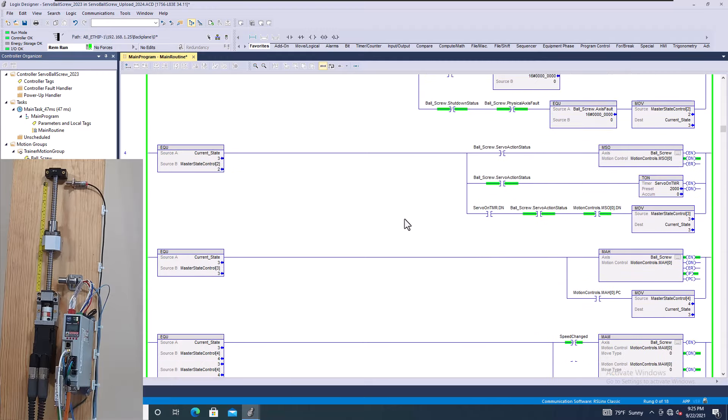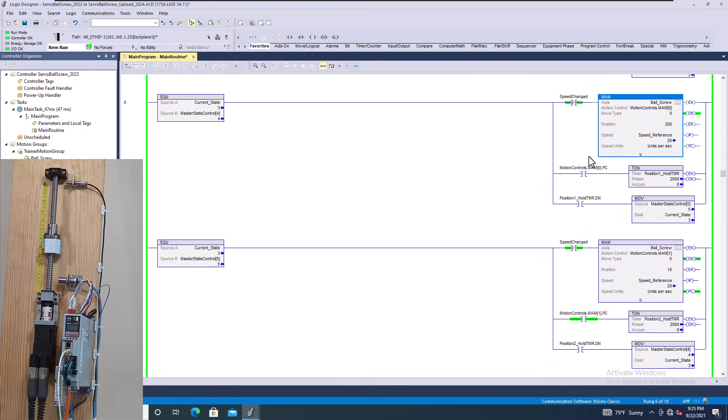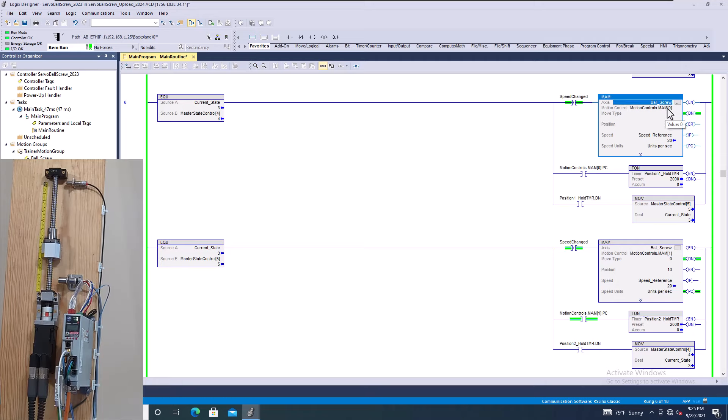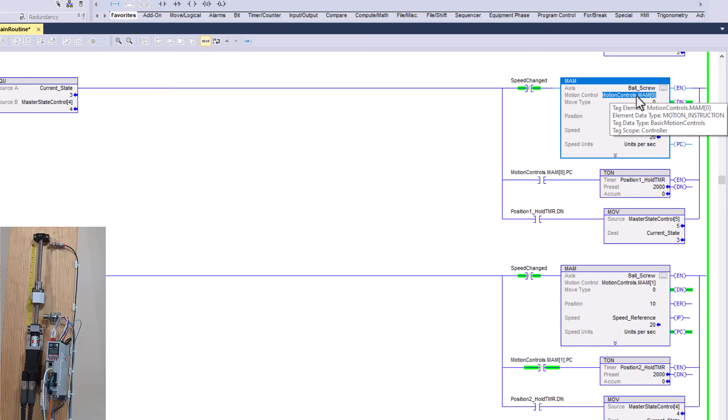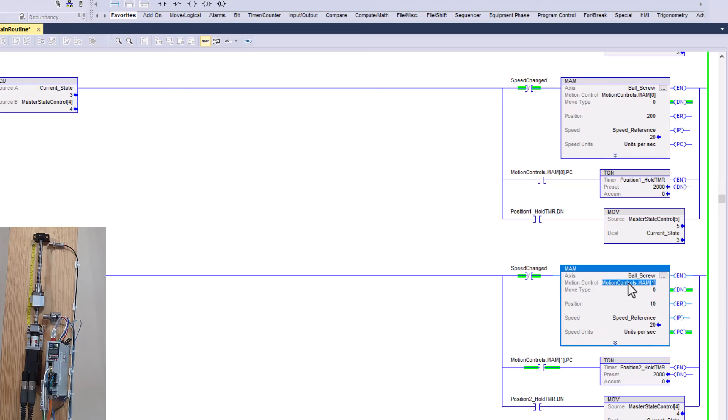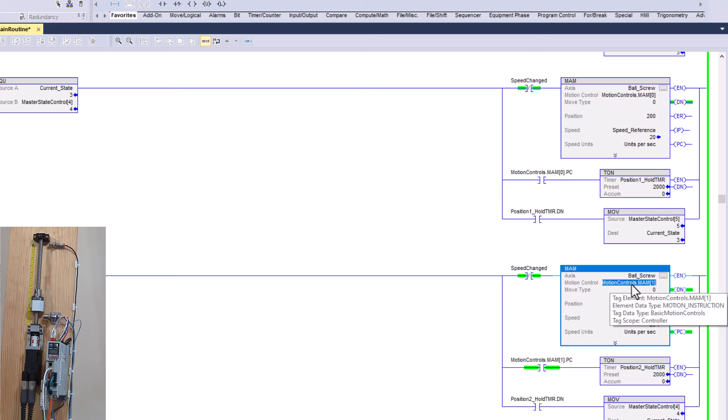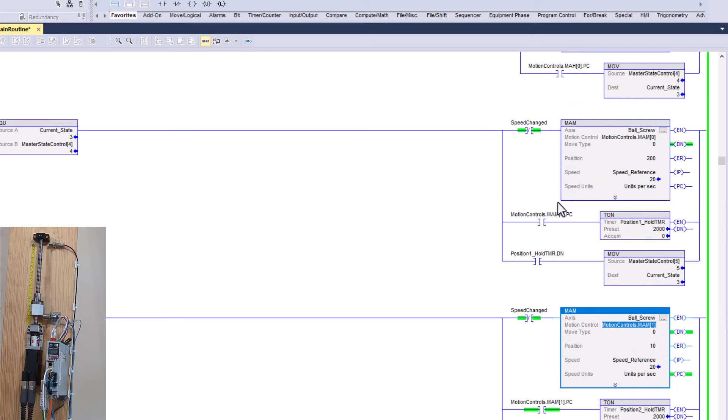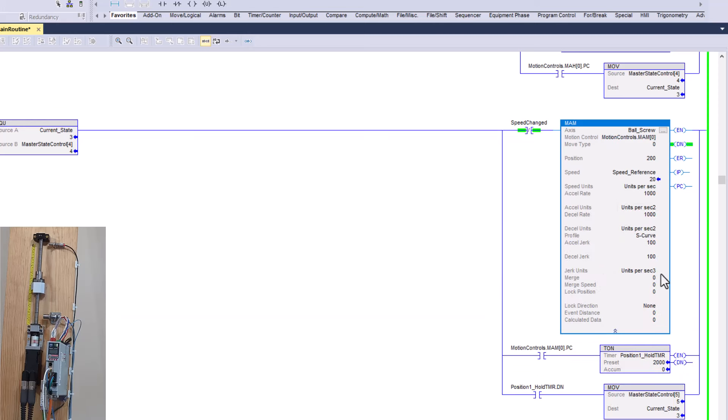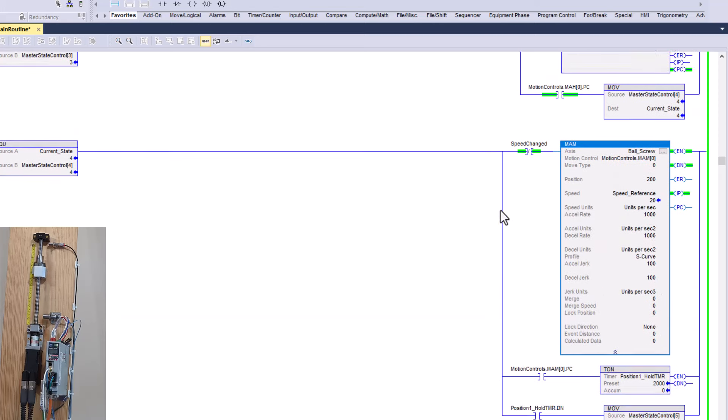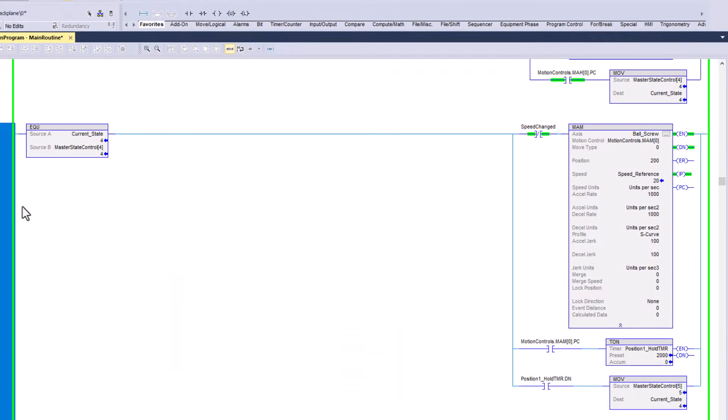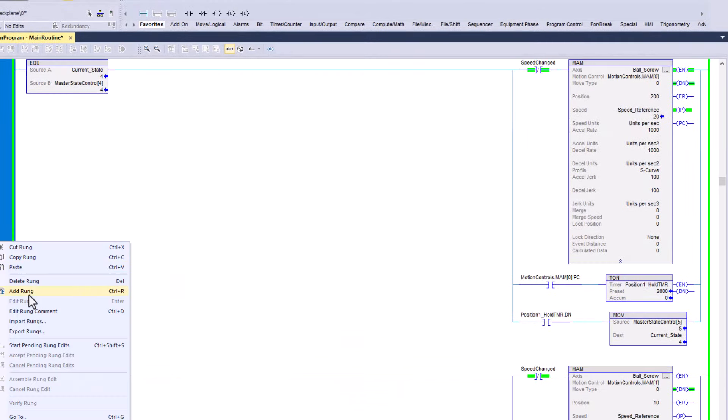What I'm trying to get at is I see a lot of times lately, and I don't know why, that people will double instructions with their MAMs. For instance, I have an MAM right here with its motion control tag as MAM zero. In my next MAM that's doing something completely different, I have it as motion control MAM one. I'm seeing that people will have the same exact instruction, the same exact attributes, tags, and everything. They literally would duplicate this whole rung and paste it in there.